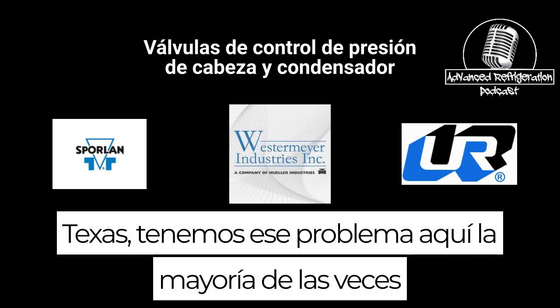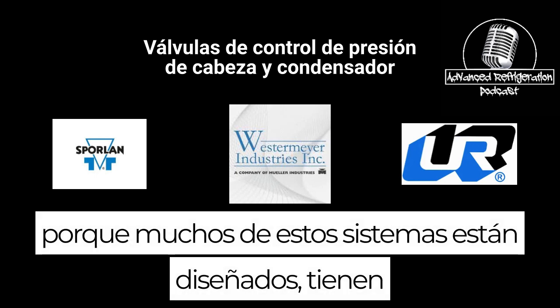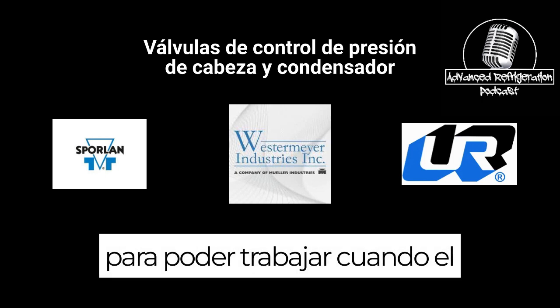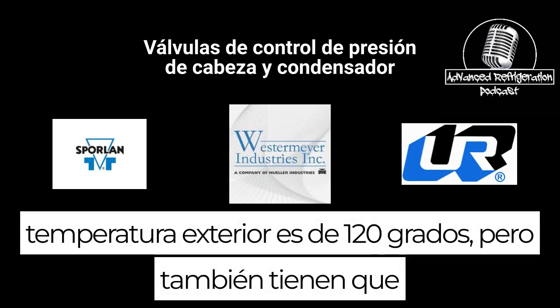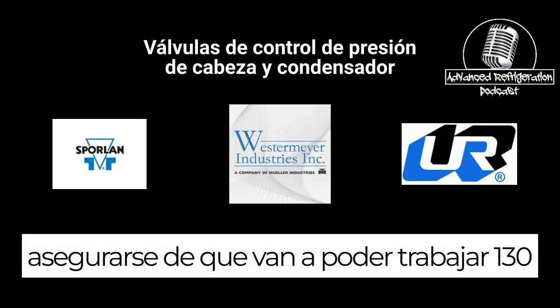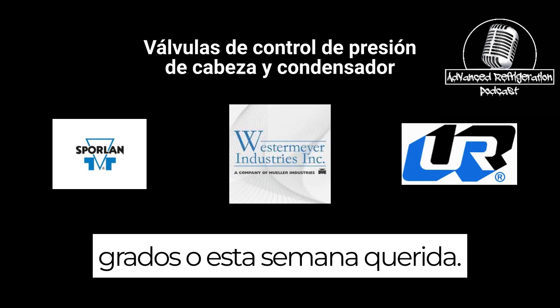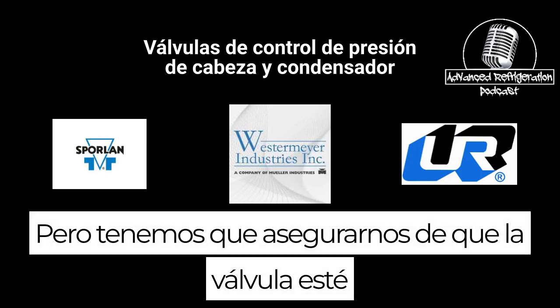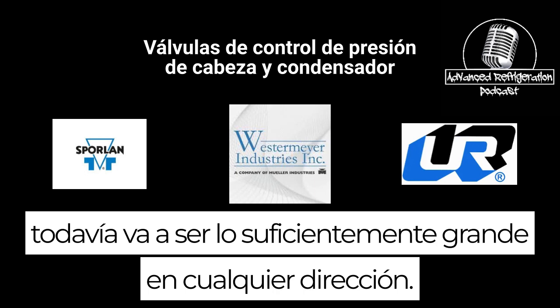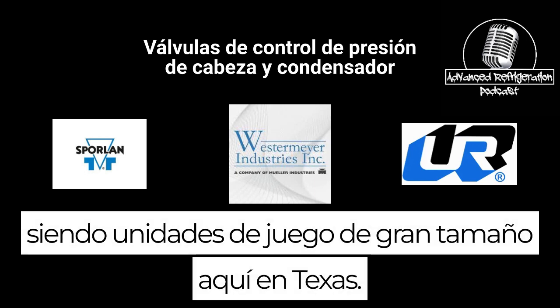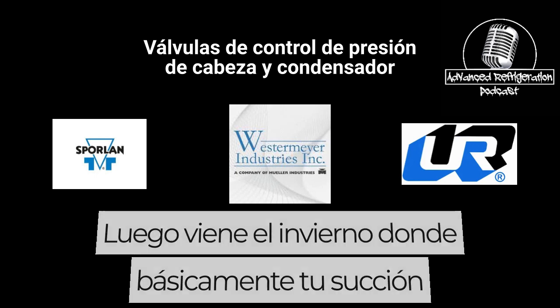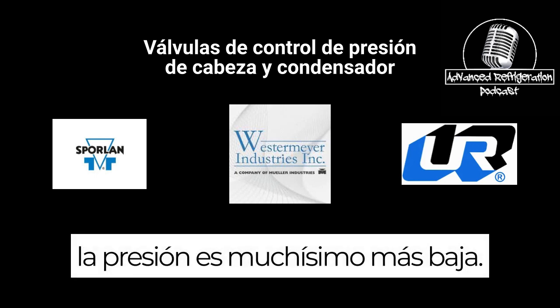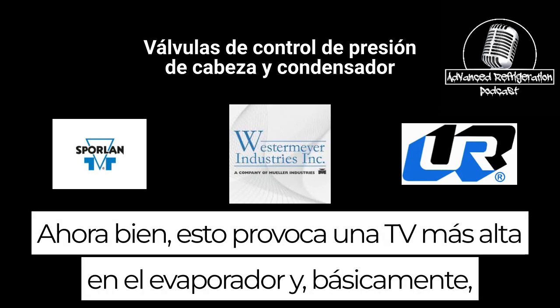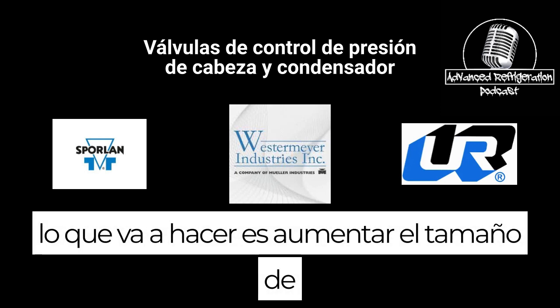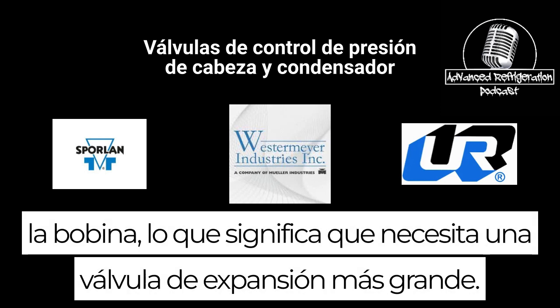In Texas, we have that problem more often than not, because a lot of these systems are designed to work when the outside temperature is 120 degrees, but they also have to make sure they're going to work when it's 30 degrees, or in this instance this week, 0 degrees. We have to make sure that valve is still going to be big enough in either direction. So a lot of times the compressors end up being oversized. Playing out in Texas, then come the wintertime, your suction pressure is a hell of a lot lower. This causes a higher TD on the evaporator, and that's going to increase the size of the coil, which means you would need a bigger expansion valve.